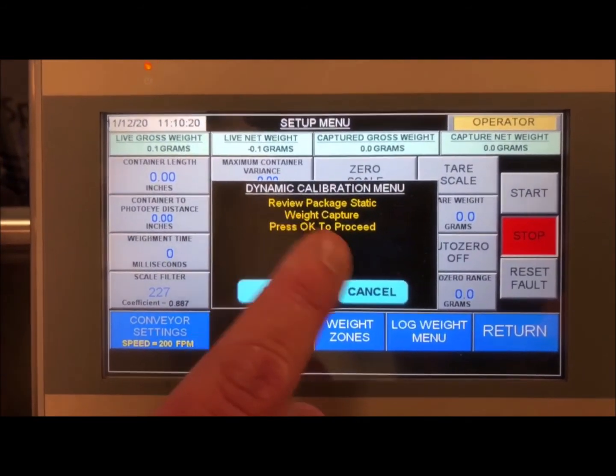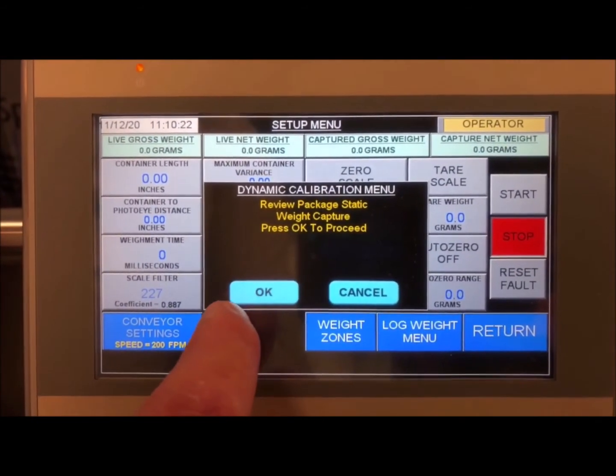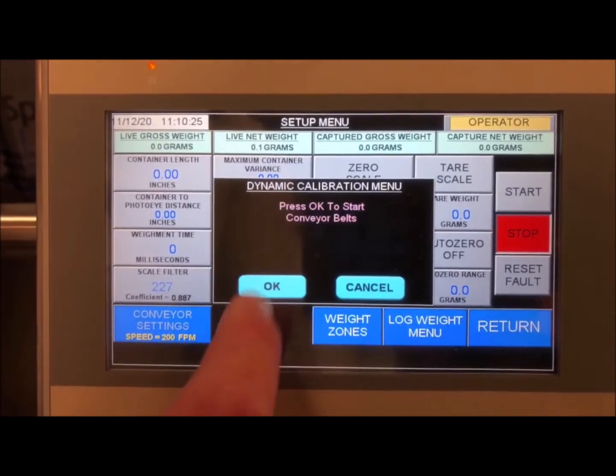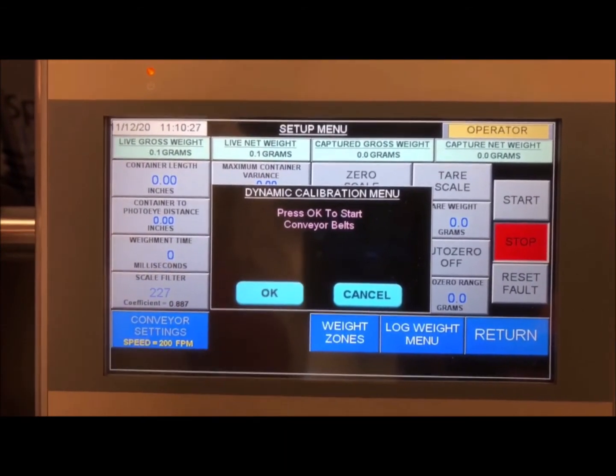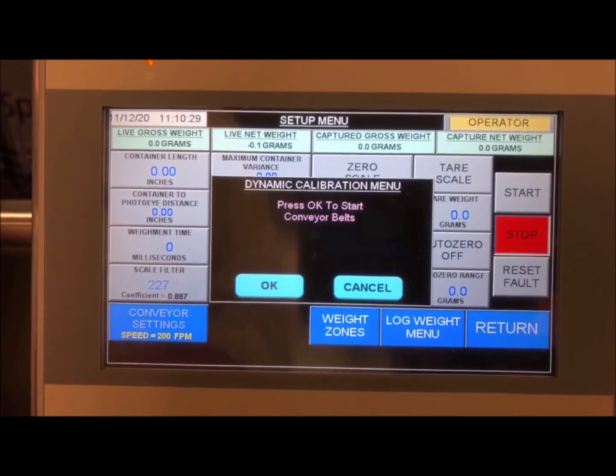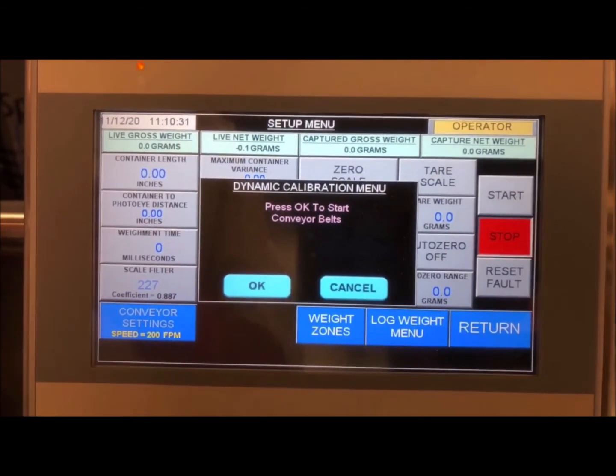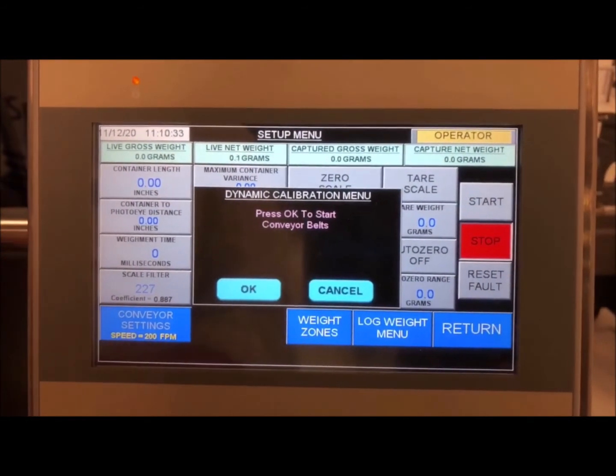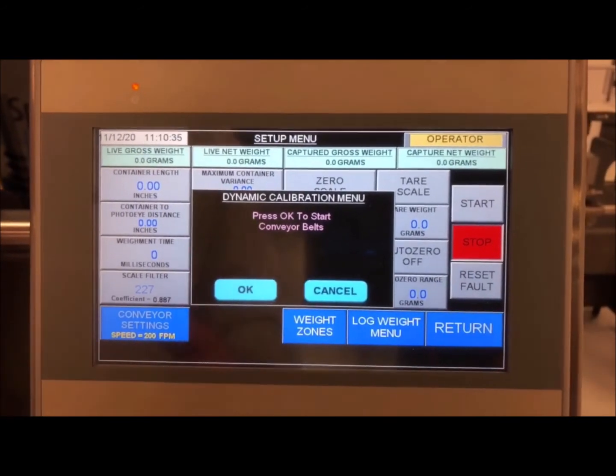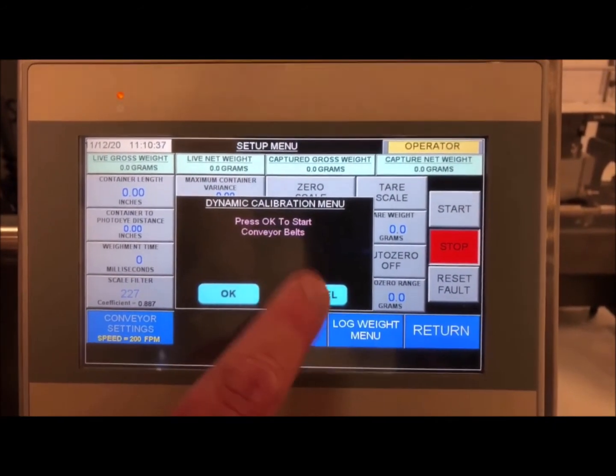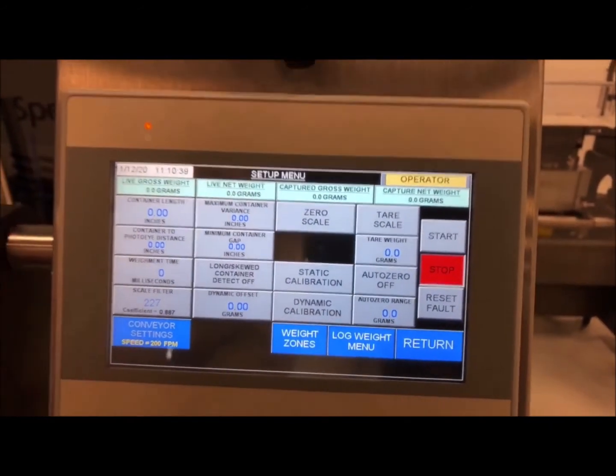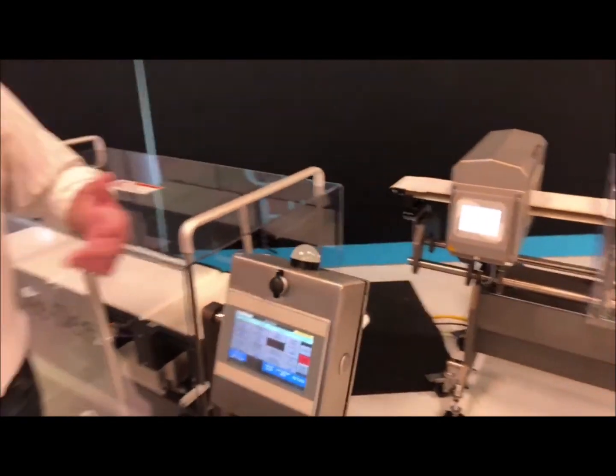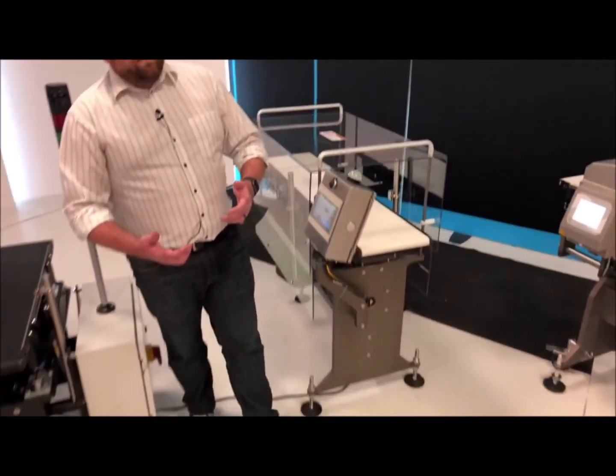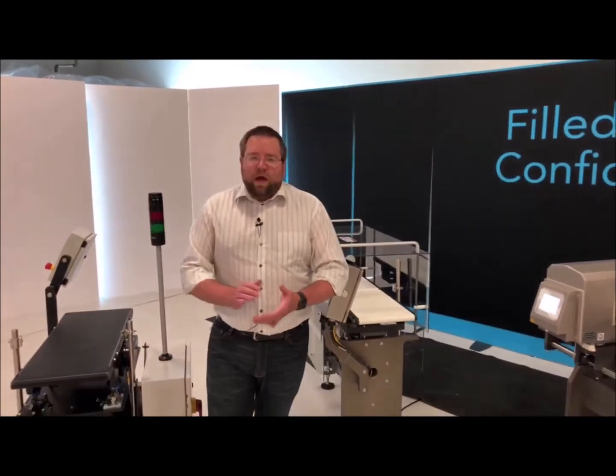Review the package static weight to capture it. You can press OK while it's on the load cell, then press OK to start the conveyor belts. You're going to run the package over it 5 times. It's going to compare the actual weight to what it reads while the package is in motion, and it'll build in your compensation right there. This is quick and simple—your operators are able to do that themselves. You don't have to have a certified technician come out to do your calibration for you. It's one of the greatest features we offer on our Evolution series.